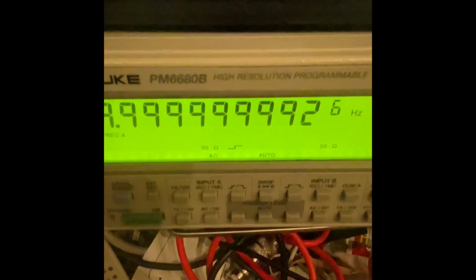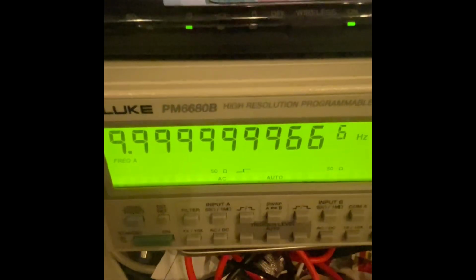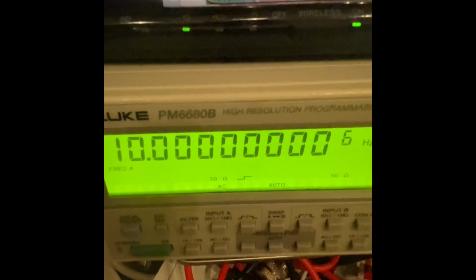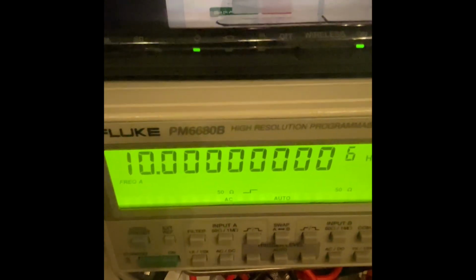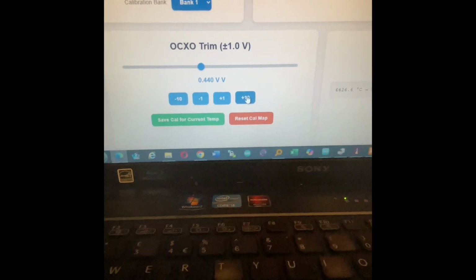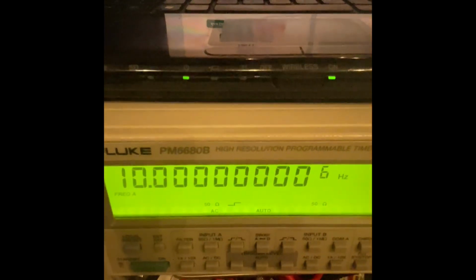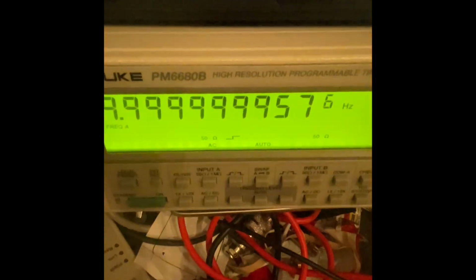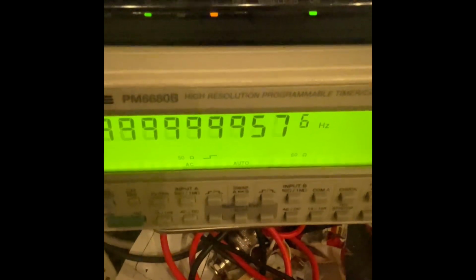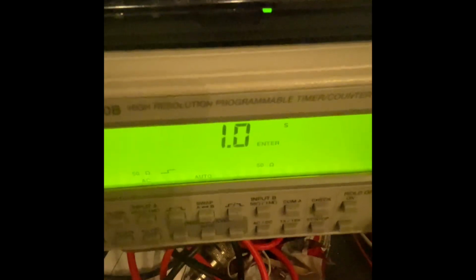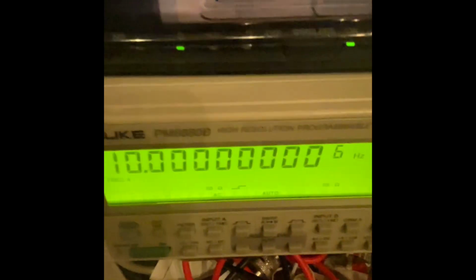So if I hit 10 on the calibration, I'm going to go up to 440, which sends this down in frequency. But this learns. It learns that we've changed frequency, and eventually it will compensate and come back up, and there we go. So it's gone back up to 10 megahertz because it knows what the trim frequency is at that temperature. So no matter what I do to this trim now, because I've locked that temperature at that particular voltage, we're always going to get back to 10 megahertz, which is really quite clever, isn't it? Even though we change the trim voltage again, because the temperature hasn't changed, see, we're way off all of a sudden, and it says, hang on a second. If we change the time base to, say, 500 milli, enter, and then we're back again.